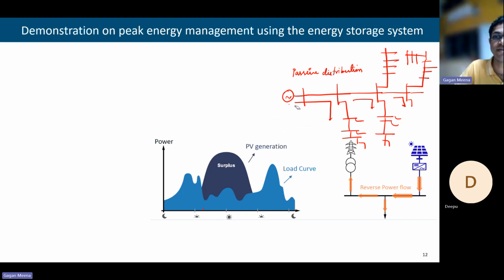But now in this active distribution system, we have distributed energy resources. We have PV plants, let's say, here. In the daytime, when the PV is at its peak and the load is also less, then the local supply is more than the demand. Let's say at a particular bus, the load is 100 kilowatt and generation is 150 kilowatts. So 50 kilowatt is more generation here than the load. Then this excess generation will go here, 50 will go here.